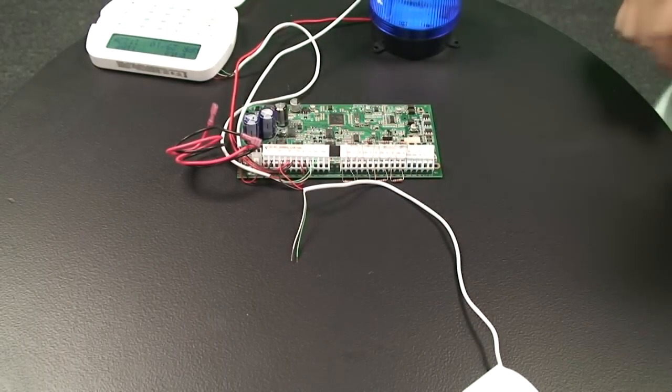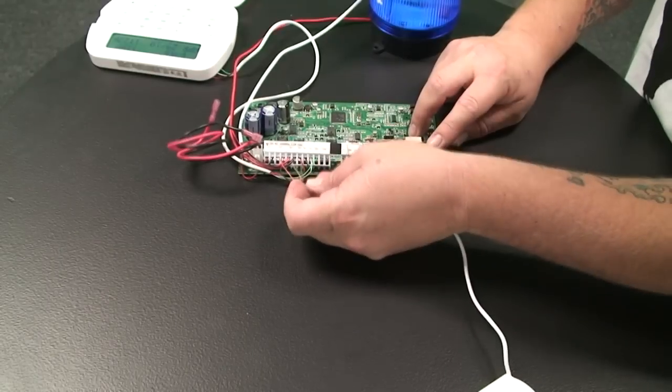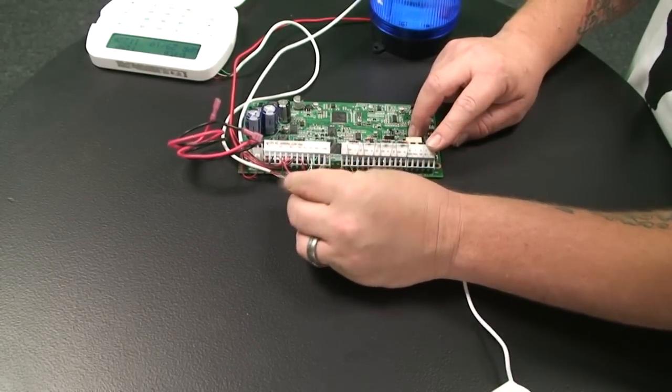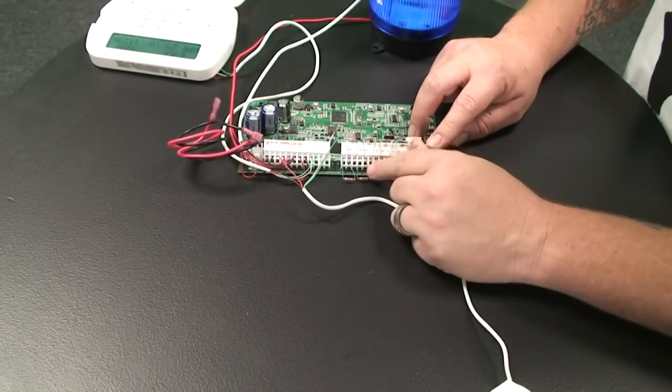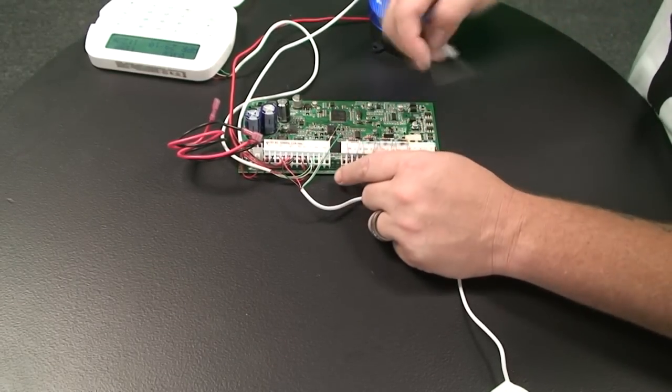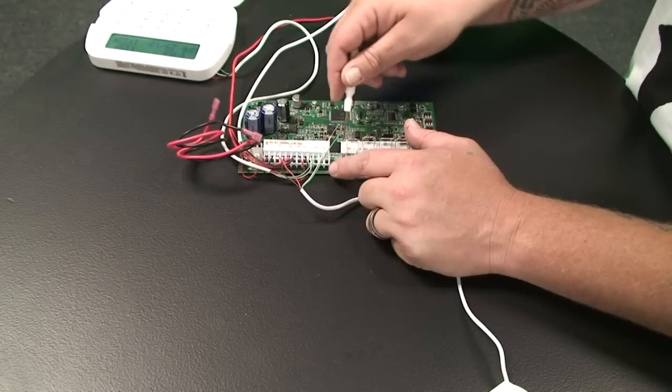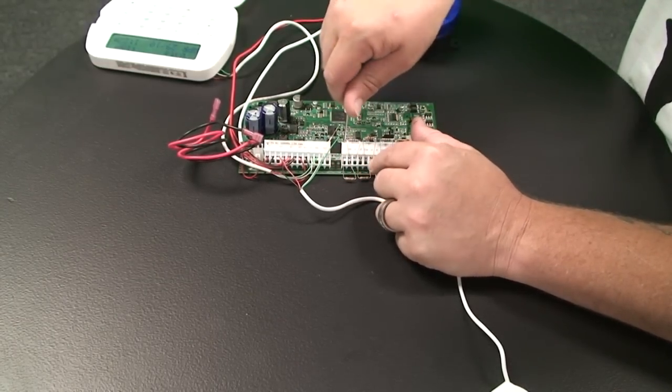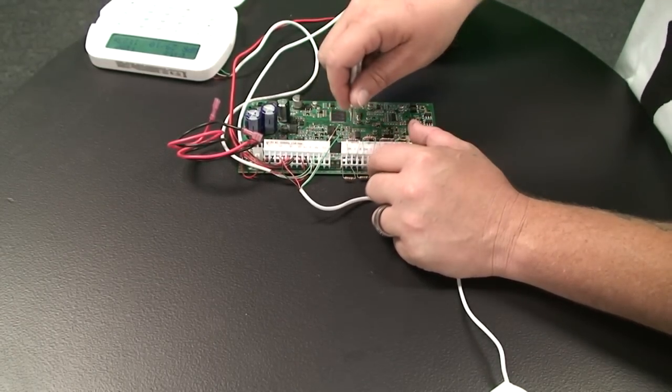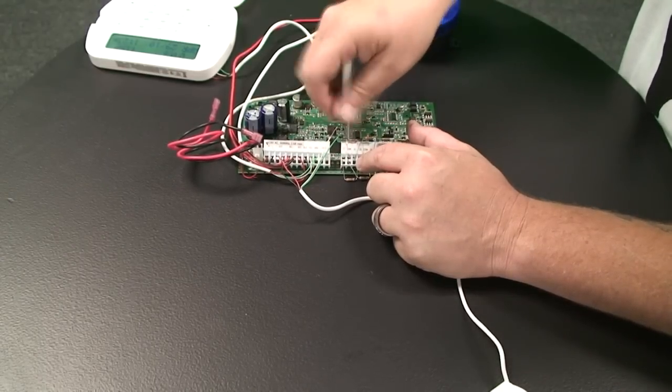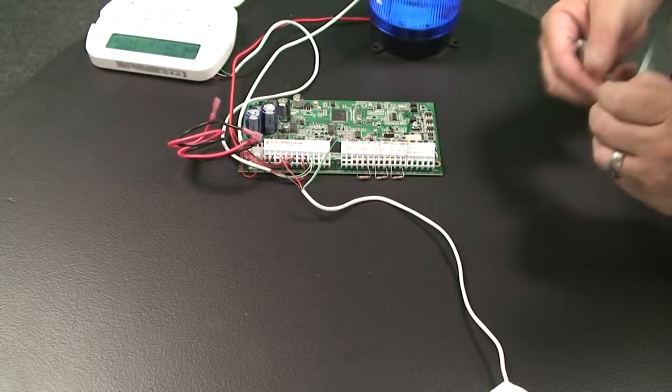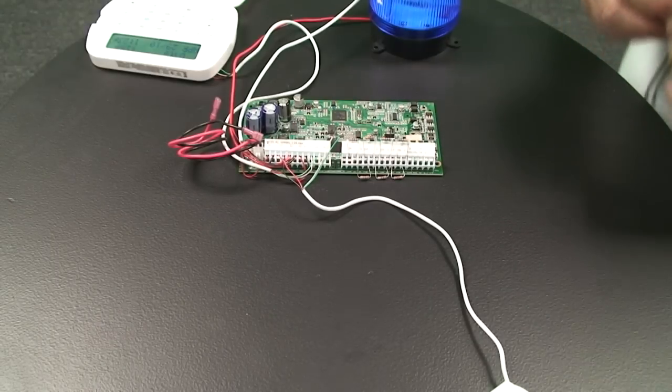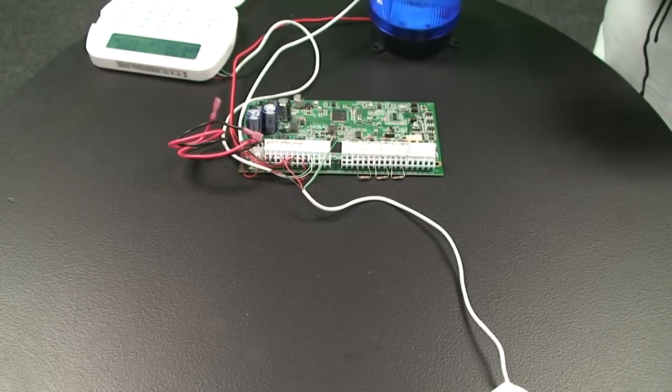Alright, so now we need to wire these other two wires here, the white and the green, that we currently hooked up to the normally closed and common in the motion into a zone on the control panel. So for this example we're going to use zone one and common. And you can see here I have a resistor shorting that zone out. So we're going to take the resistor out and we're going to use this particular resistor. We're wiring this up to the control panel.